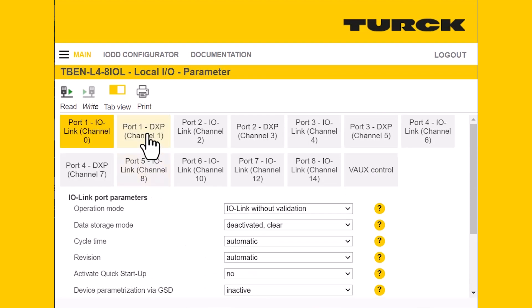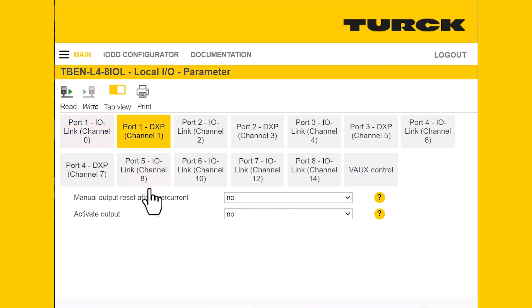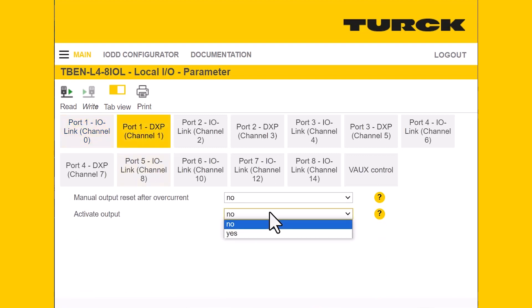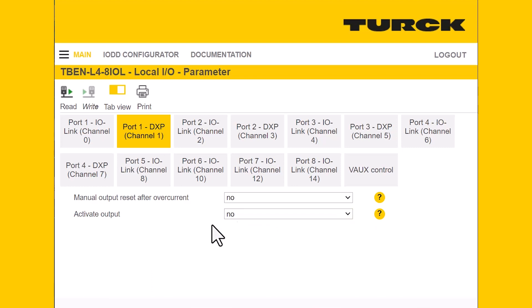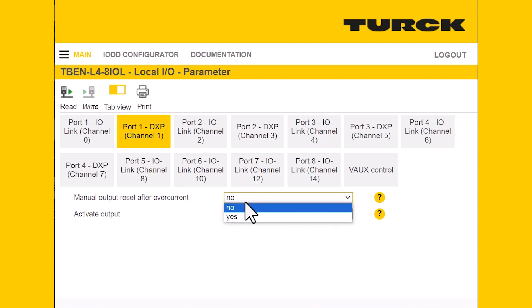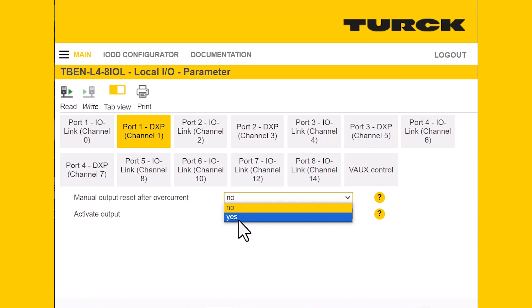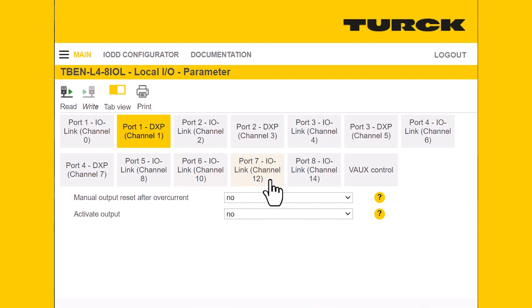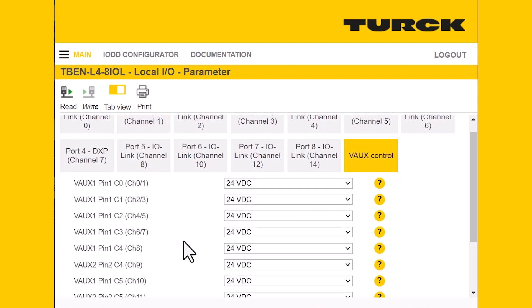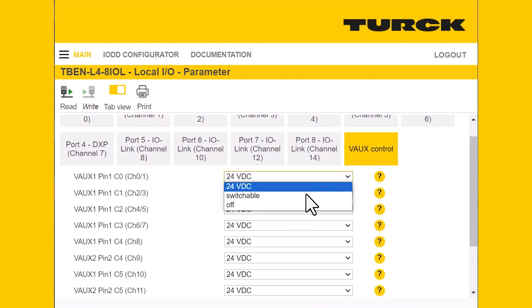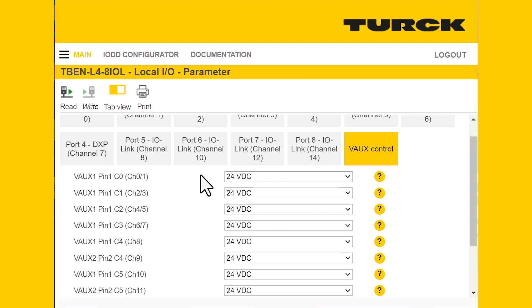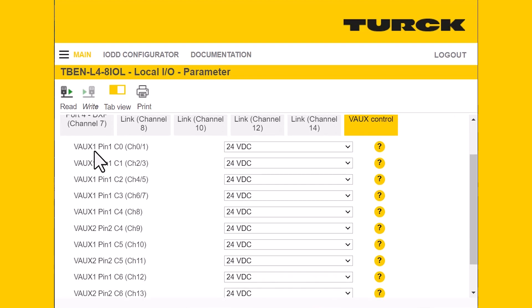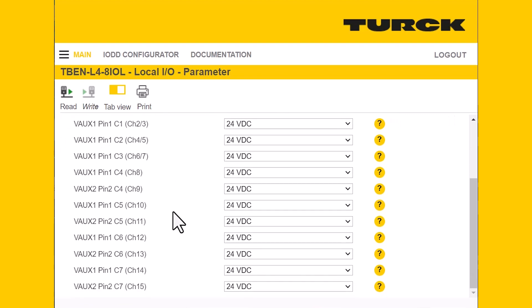To give you an example, we'll go to one of our DXP channels. For this, you can essentially just activate the output or not, or choose to have a manual output reset if there's an overcurrent. And to show you everything, we'll go to VAUX control, where you can set whether you want 24VDC switchable or off for any of your auxiliary power outputs. It tells you the specific pin and port you're working on.